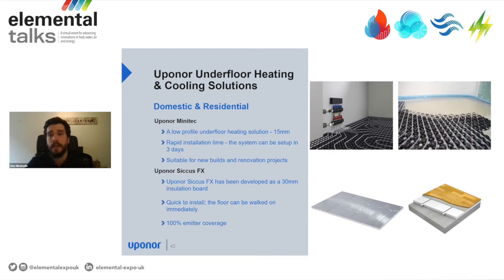The pipes can be laid inside the upper side of the panel, which is routed. On top of the panel and the pipes, something like a leveling compound or something similar needs to be poured with a minimum thickness of 15mm and a maximum recommended thickness of 30mm in order for the system to maintain its high efficiency and performance. The benefit of the system is that it is a very high response system with high performance for both heating and cooling.